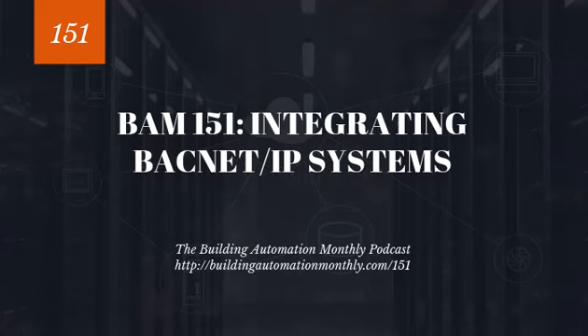So a device is an object, and a device has objects. Some common objects are analog values, binary values, analog inputs, analog outputs, and different objects have different properties. Some properties are present value, the priority array, the text, the device ID, the object ID, etc.